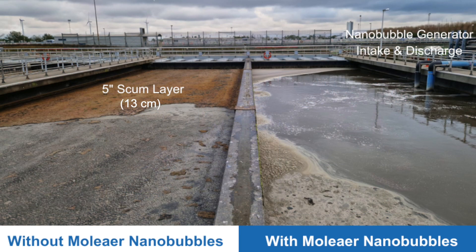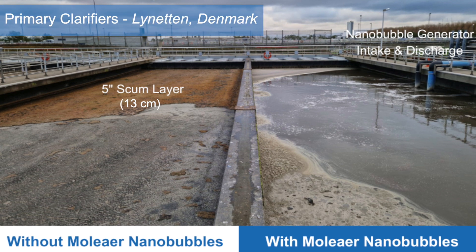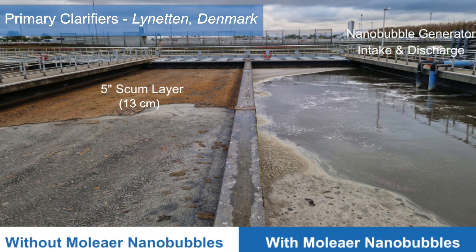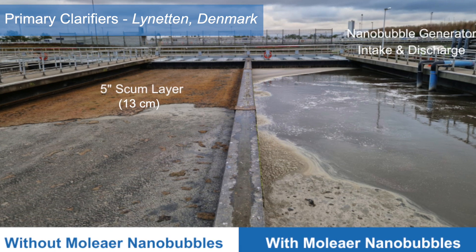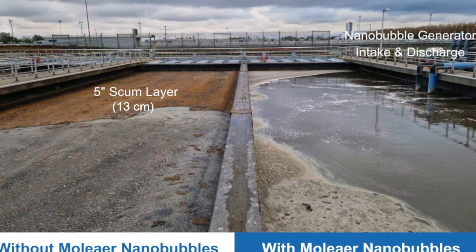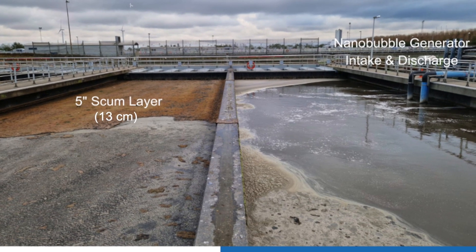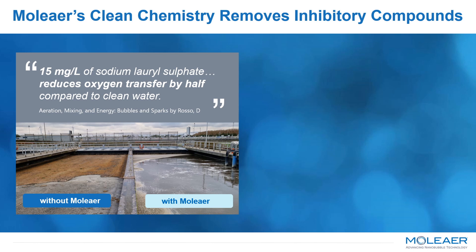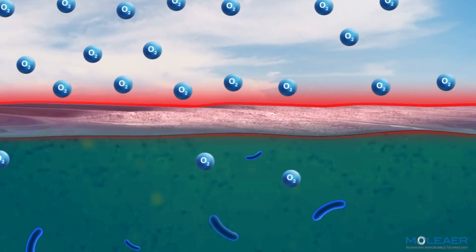In this example, the complete removal of the scum layer on the primary clarifier within less than one week of operation is due to the breakdown of those surfactant compounds that were creating a jelly-like stable emulsion at the surface of the water. The scum layer impedes natural oxygen transfer at the air-water interface. In the literature by Diego Rosso entitled 'Aeration, Mixing and Energy: Bubbles and Sparks,' it states that sodium lauryl sulfate, a common surfactant, has been shown to impede oxygen transfer by 50% at concentrations as low as 15 milligrams per liter.